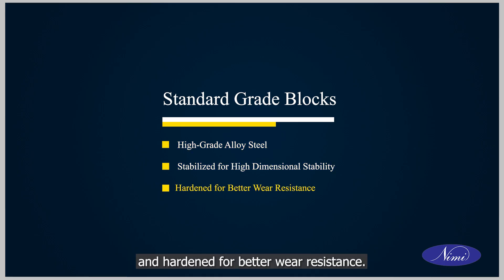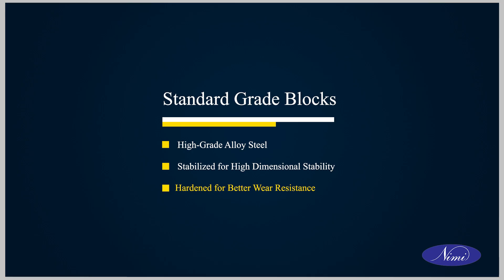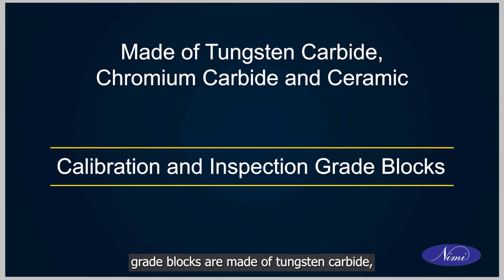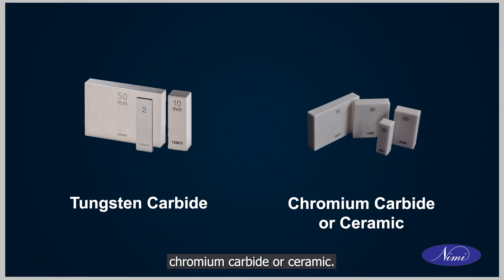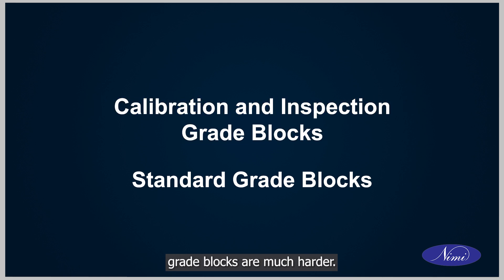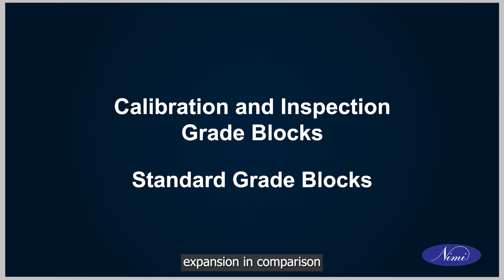For high degree of accuracy, standard grade blocks are made of high-grade alloy steel, stabilized for high dimensional stability and hardened for better wear resistance. Calibration and inspection grade blocks are made of tungsten carbide, chromium carbide, or ceramic, which are much harder with high wear resistance and low thermal expansion in comparison with standard grade blocks.